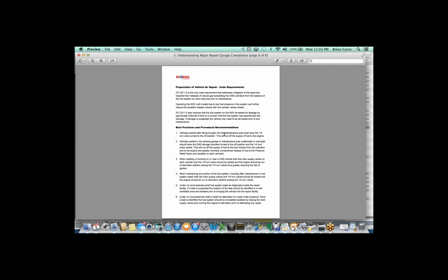And typically, in my 6 bullet points here: number 1, vehicles parked after being brought into the shop shall have that quarter turn valve turned to the off position. That's obviously the valve that supplies gas to the engine. These are attended vehicles in the shop requiring maintenance. Number 2, vehicles parked in the shop, garage or maintenance area unattended or overnight should have the CNG storage cylinders turned to the off position and the quarter turn valve closed. And then you're going to stall the engine to use up any fuel that's between either the quarter turn valve or the main tank valves.